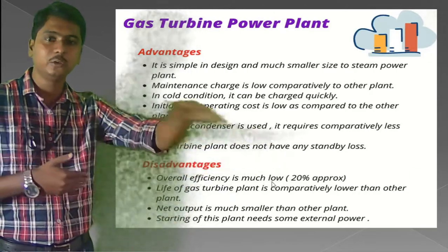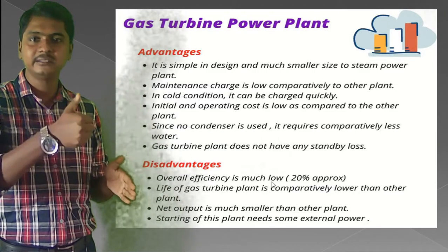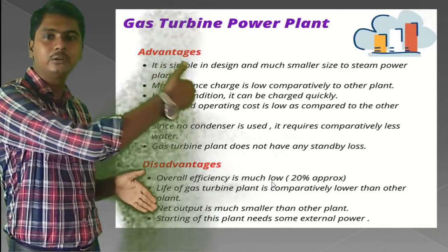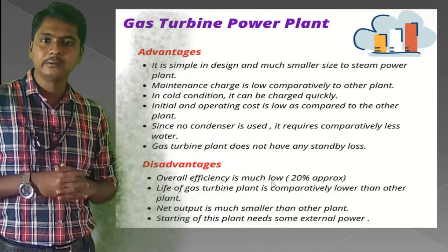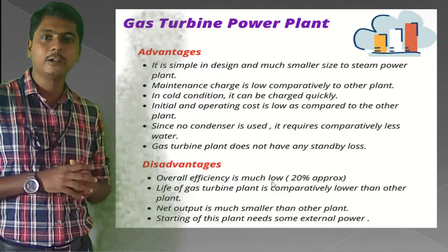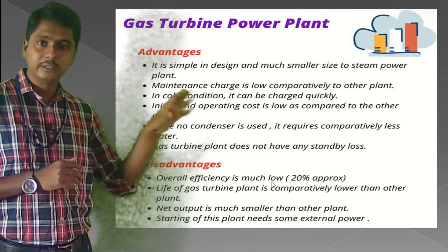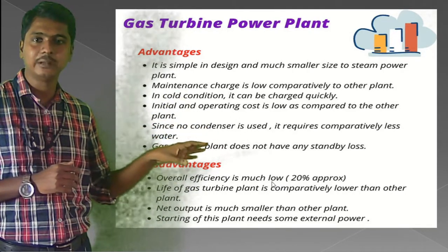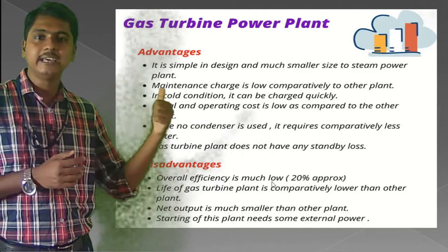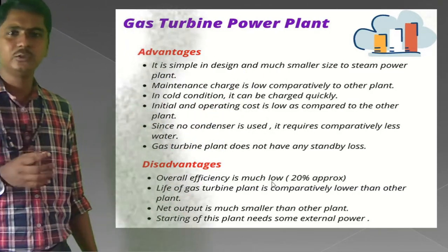Whatever floor space is required in a gas turbine will be very less, which results in less expense for a gas turbine power plant as compared to a hydraulic power plant. And one more thing, there will be no standby losses for a gas turbine power plant as compared to a steam power plant. Maintenance cost is also very low. And the cold starting problem will not come into the picture in a gas turbine power plant as compared to a steam power plant. Those are some advantages you can see.